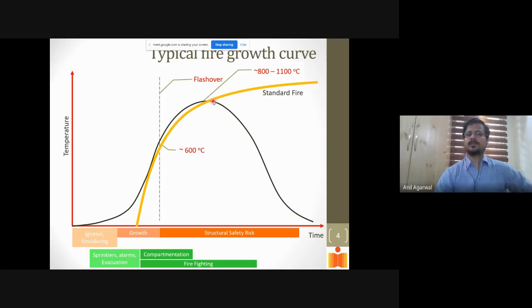So if we conduct a test for 1 hour, basically here in a furnace, the fuel is not stored inside the furnace. Fuel is pumped into the furnace as the fire grows. The fuel could be LPG, mostly, rather than CNG, or LNG, liquid natural gas, or it could be kerosene, or some other petroleum that is pumped into the furnace while the fire is going on. So there is no reason why the fire should die out, because you can always keep pumping the fuel.